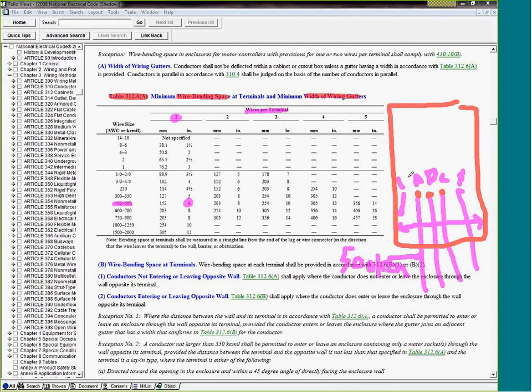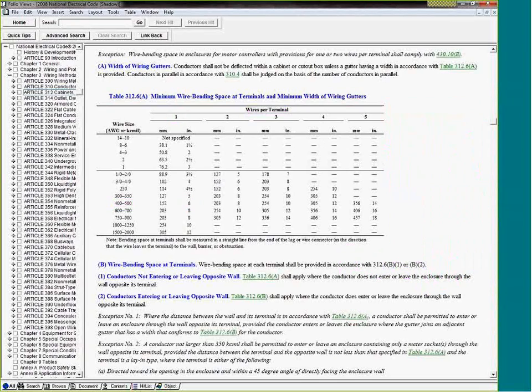I know it'll be wider because of the overcurrent device on the buses, guys. But that's the gutter. Usually, guys, right in here is where it is. This is the space right in here. If I'm bringing conductors, this is the gutter I'm trying to size, around the circuit breaker. This is the circuit breaker. So it's basically 6 inches wide. Anything else about this? How to use this one? Any questions? How about the next for Chad? Make sure they're with me. Okay, great. I'll go erase this one and give you an example, guys.